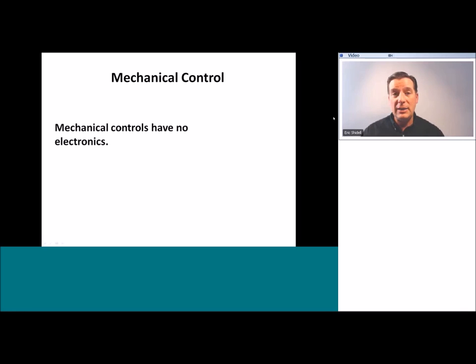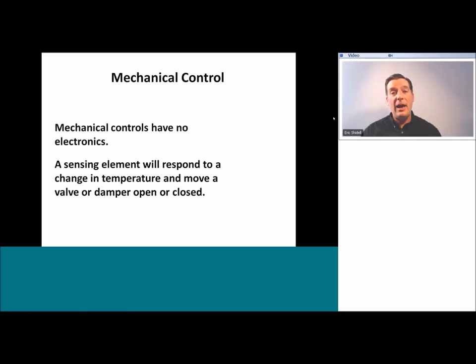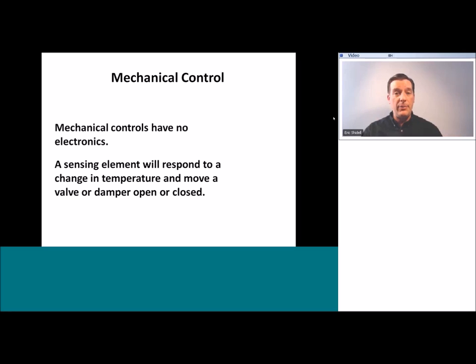Mechanical controls have no electronics. The next phase of evolution beyond manual control was mechanical control. Mechanical controls have a sensing element that responds to a change in temperature, and it will physically move a valve or damper open or closed — duplicating the action of manual controls. In the manual control, the sensing element was you, your physical sensation. In a mechanical control, the human sensing element is replaced by a mechanical one that takes over that motion in response to temperature.